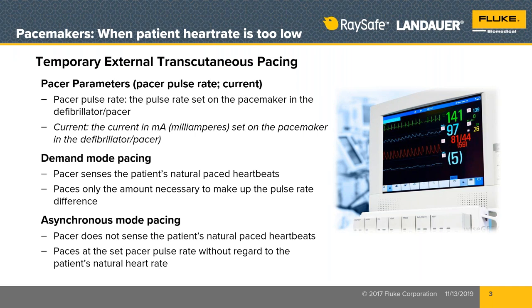So when we look at the temporary external, transcutaneous is a big word. It just means through the skin. So we're either going to pace through the pads or paddles that we would also defibrillate through, or sometimes there is a separate set of little electrodes that stick onto the patient for the purpose of doing this pacing. The pacer parameters are current that we're going to dial into the pacemaker part of the defibrillator, and a pulse rate. So it will be in pulses per minute, and that will be how we assess how much we're causing the heart to beat in addition to the much slower natural heart rate of the patient when we need to do this.